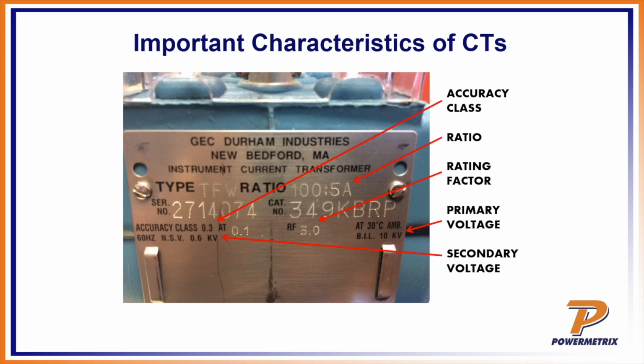We got the rating factor there. We're going to talk about that in a minute. If this is a 100-to-5 CT and I have a rating factor of 3, I can actually put 300 amps on that CT. Okay, and we're going to talk about the rating factor more in a minute. And then primary voltage, it'll tell you what voltage this CT is made to run at. And then you've also got the secondary voltage. It shows you over there on that left side.